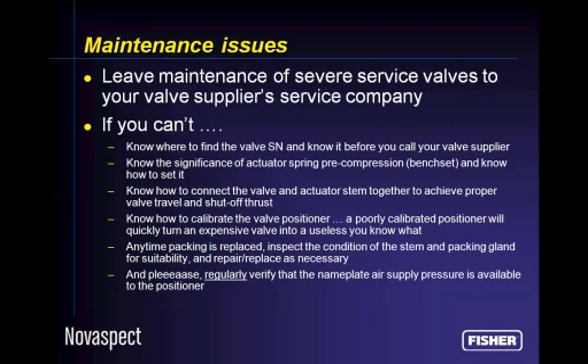Know where to find the valve serial number and have it before you call your valve vendor, because they're going to need that to give you recommendations about how to take care of this, what parts go into it, and so forth. There's an adjustment in most control valves called the spring precompression. We call it the bench set. You need to know the significance of that and know how to set it. Customers frequently set that incorrectly. We end up with valves that start leaking through immediately and have significant trim damage.